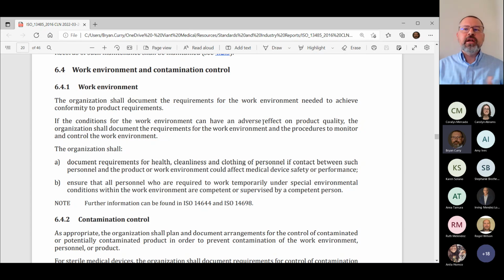So if you've ever been involved in clean room monitoring and you've heard them talking about air and surface viables, that is the routine monitoring that we're going to see here, and the standard requires that we perform it to demonstrate ongoing control of the work environment and contamination control. We're trying to demonstrate that the anticipated bioburden baseline has not drifted too far from where it was when we validated the sterilization validation and the clean room itself.